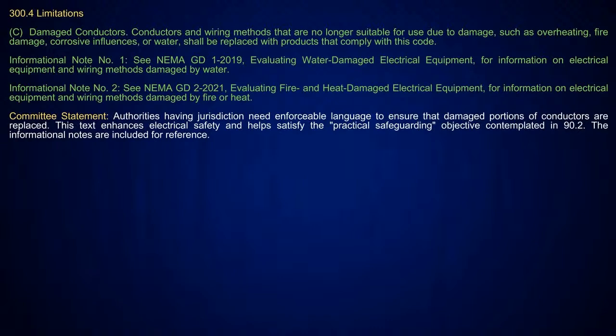Now, this one is where they have placed enforceable language. This is to take care of where you could have damaged conductors. They're basically telling you here, when you have conductors and wiring methods that are no longer suitable for use due to damage, such as overheating, fire damage, corrosive influence, or water, they are required to be replaced with products that comply with the NEC.